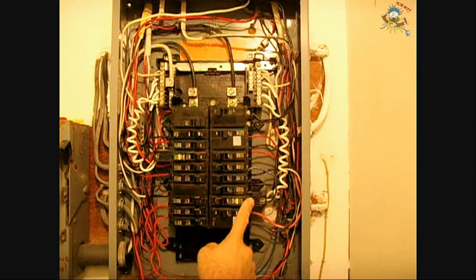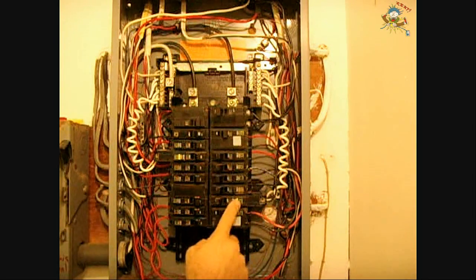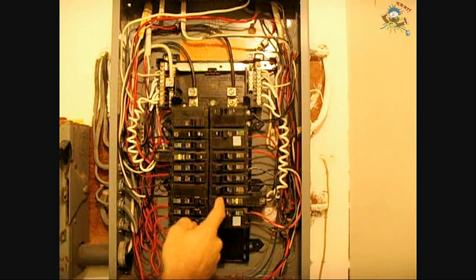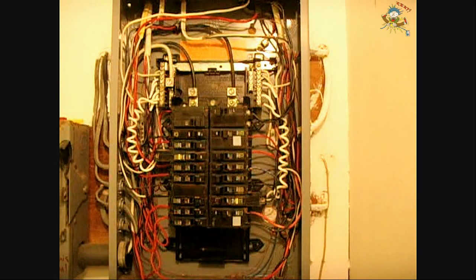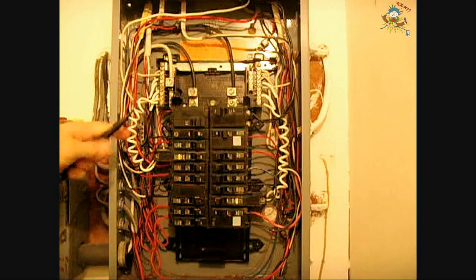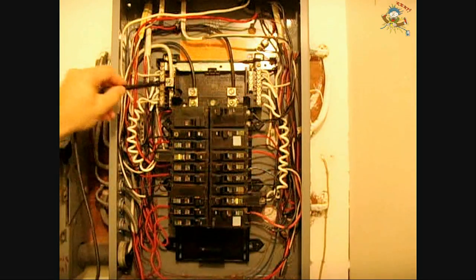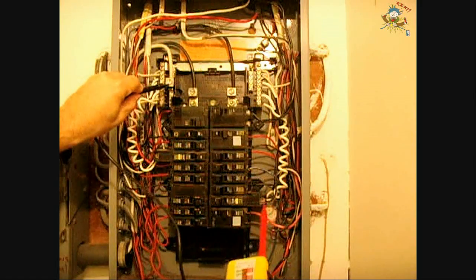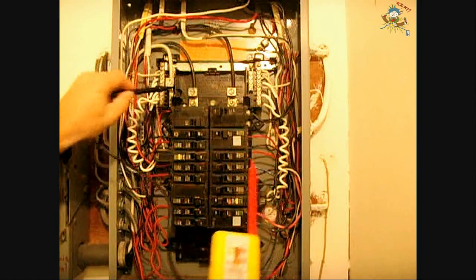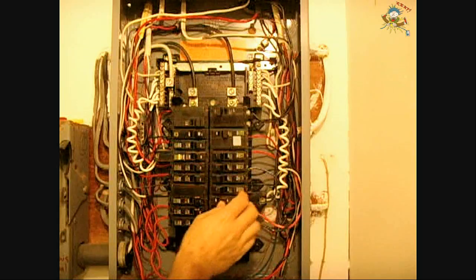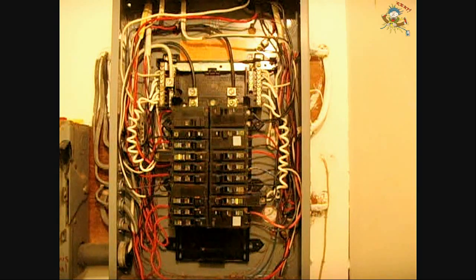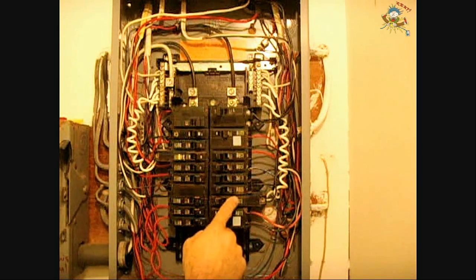Now the breaker you're looking at right here, the GFCI, has a self-test on it, alright? You push that button to test it. You can also test it without pushing that button. You could have one wire going to either the ground bar or your neutral, and then you could touch the screw. It should trip. Alright, it works perfect. Now the reason why it tripped is because it's simulating exactly what this button's doing.